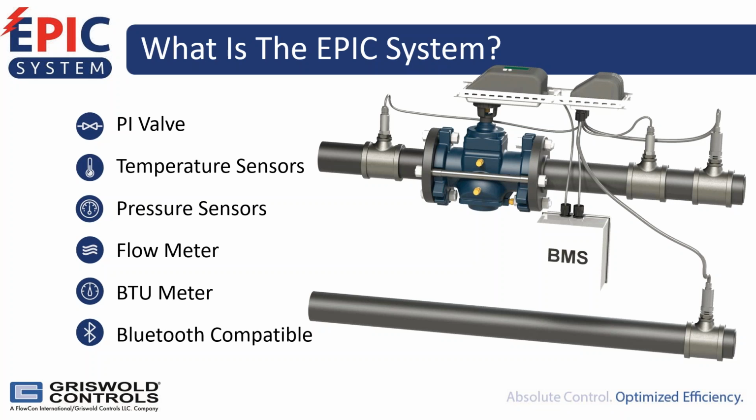There are also pressure sensors, so we can measure the pressure across our pressure-independent valve. And then within that, there's a flow meter with the pressure-independent valve that tells what the flow is based on the pressure sensors as well as the actuator position. And because we now know what the flow is and we know what the temperature drop is across the equipment, we can now calculate what the BTU heat transfer is for that piece of equipment.